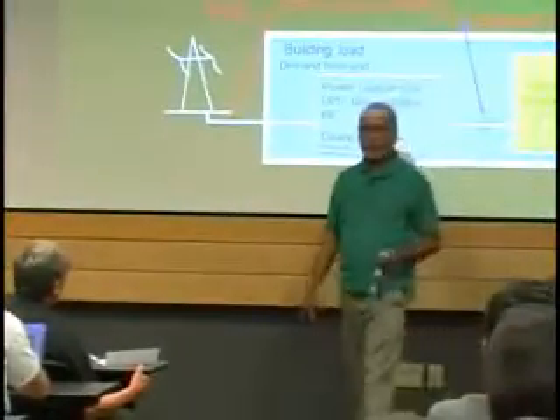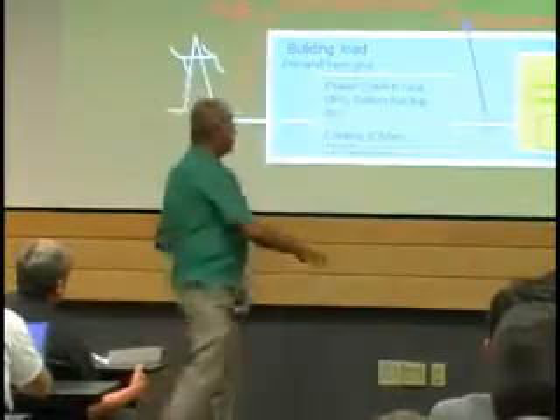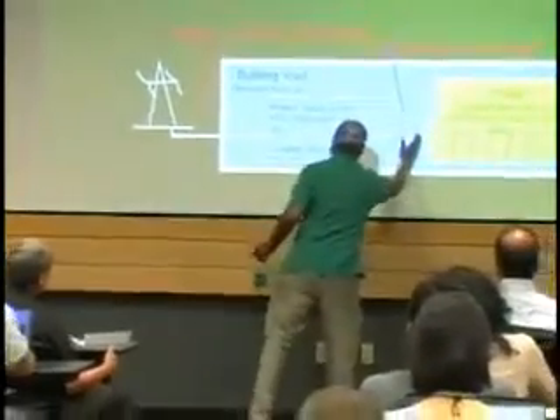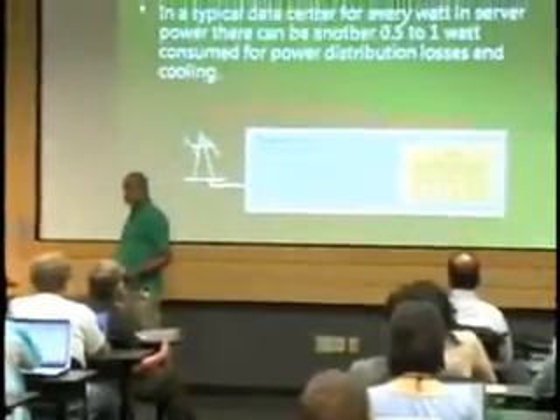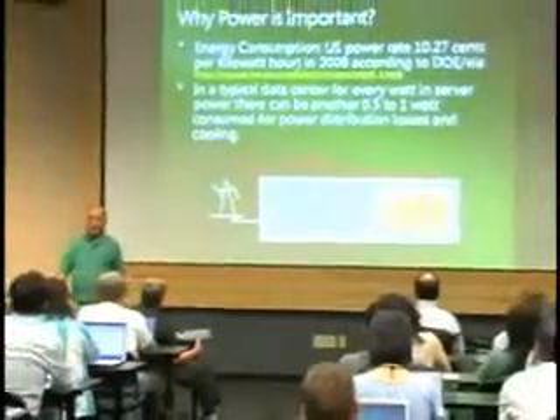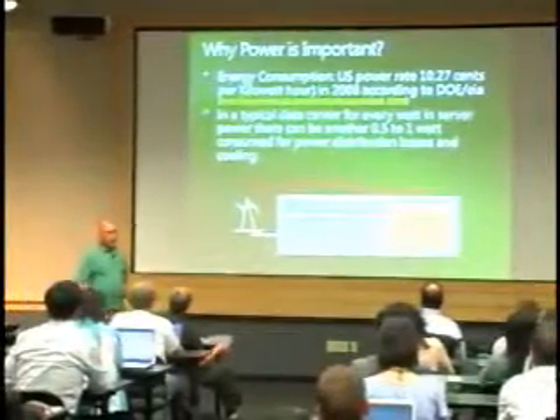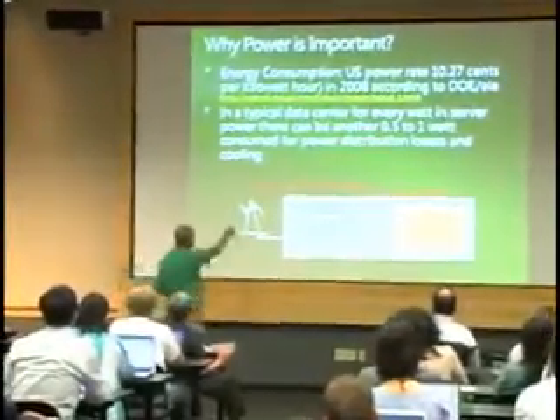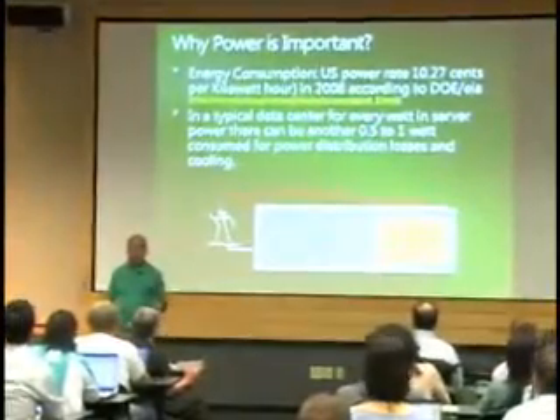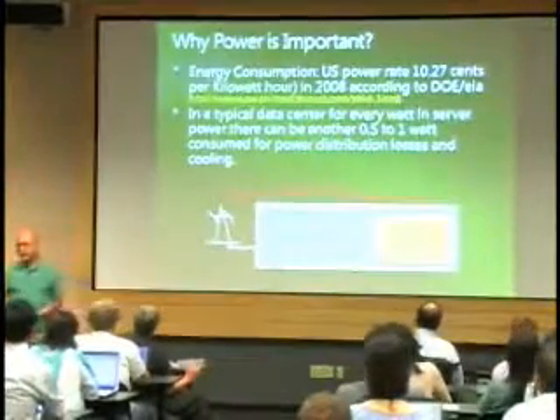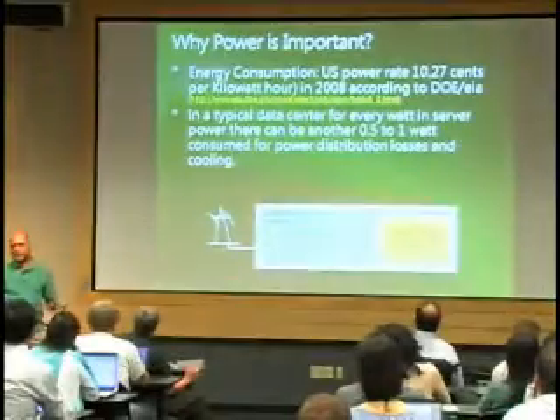The other thing to remember is there's a metric called PUE, or power usage effectiveness. What that says is we usually look at the power consumed by the servers and network equipment, but for every watt consumed there, the rest of the system, from the utility down, consumes somewhere between half a watt and another full watt. The industry average is more than 1 watt, which means the PUE, that ratio, is greater than 2.